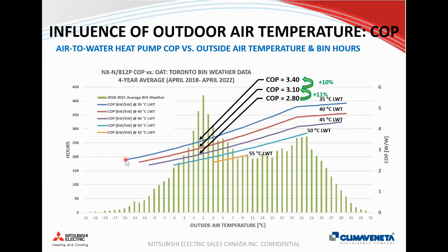So we need to look at it holistically whenever we're trying to do decarbonization and electrification. We can't just take all the gas boilers in the world and change them to electric boilers and call it a day. That's not a scalable solution. So air to water heat pumps will have a part to play, and partial fuel switching is one of the good applications, where even using it down to -5, you can still get good efficiencies, above 2.5 or so, 2.7.